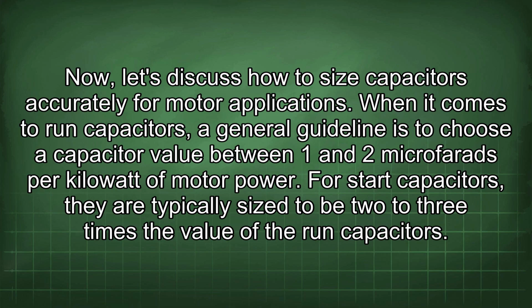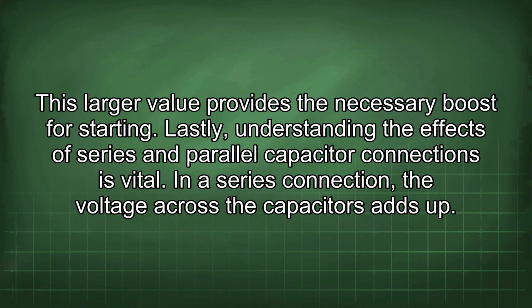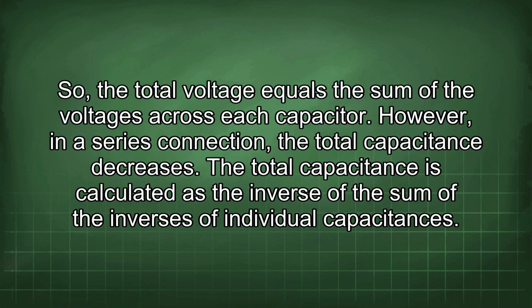For start capacitors, they are typically sized to be 2 to 3 times the value of the run capacitors. This larger value provides the necessary boost for starting. Lastly, understanding the effects of series and parallel capacitor connections is vital. In a series connection, the voltage across the capacitors adds up. So, the total voltage equals the sum of the voltages across each capacitor.